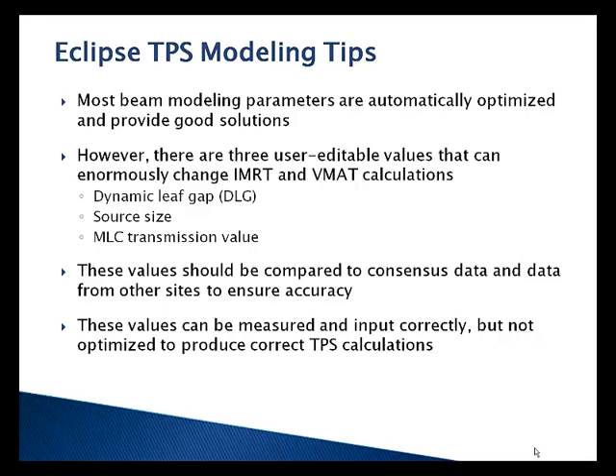So, very specific tips for modeling in Eclipse. I know this is not something that most dosimetrists end up doing, but everyone can look back at their beam model and see if these are correct. Eclipse actually is a fairly easy system to model in. Varian does a lot of things behind the scenes that does a good job automatically. But there are 3 numbers in Eclipse that you really have to pay attention to because they can enormously change your results: dynamic leaf gap, the source size, and the MLC transmission value.